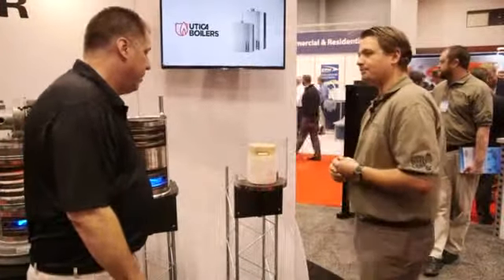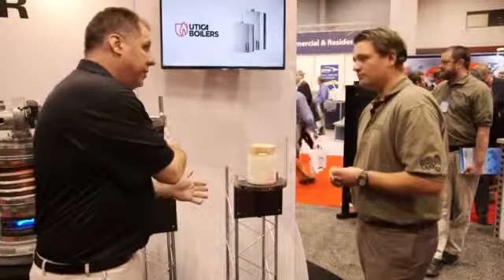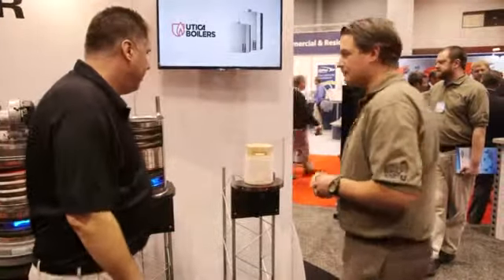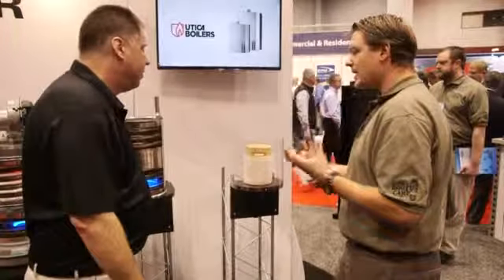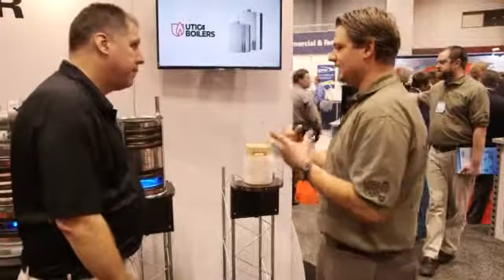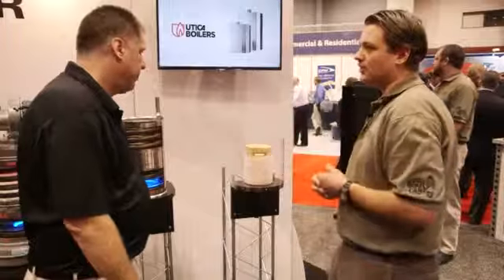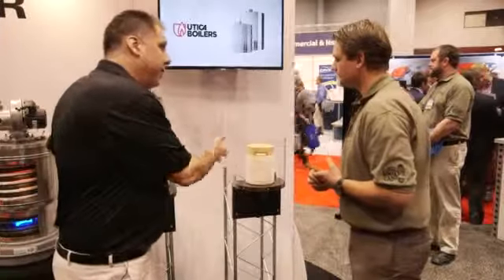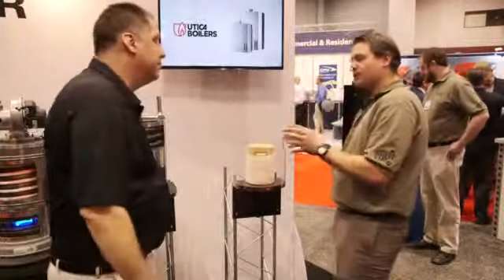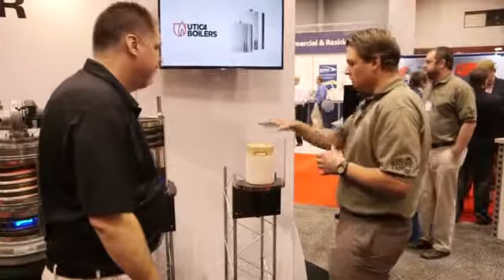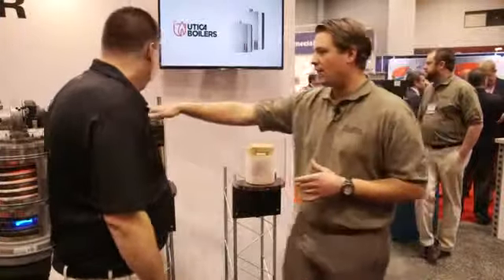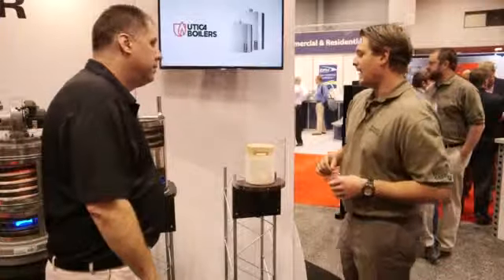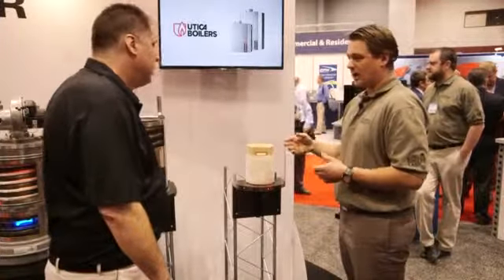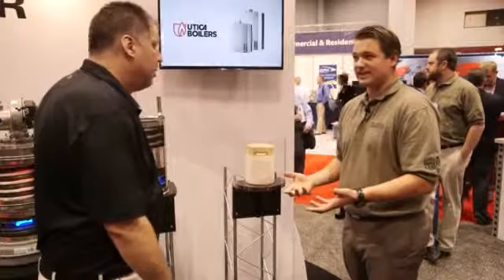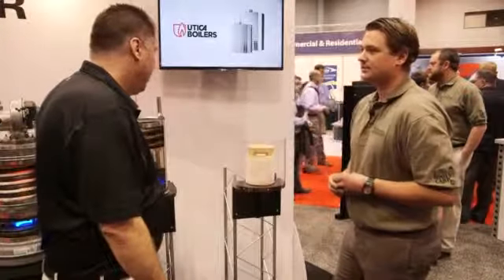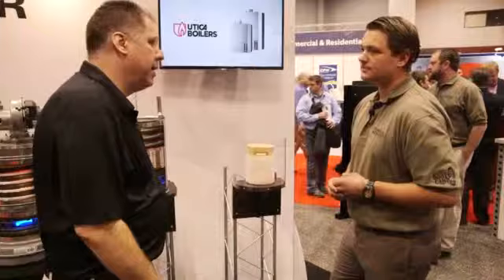And this is something your engineers innovated specifically for this heat exchanger? Specifically for this, yeah. To maximize the efficiency. It does. It maximizes the efficiency. It actually takes the heat and disperses it evenly over the coils. Is this something you ever need access to or servicing? Or you don't have to service it, it's built right into the heat exchanger. You would be able to see this from the top. If you were to take the top off, you'd look right down and see that. And any of the cleaning that needs to be done would be in the base, which is a self-cleaning design, so it's taken care of by the product. Right, so it makes it very simple to maintain and operate this boiler.